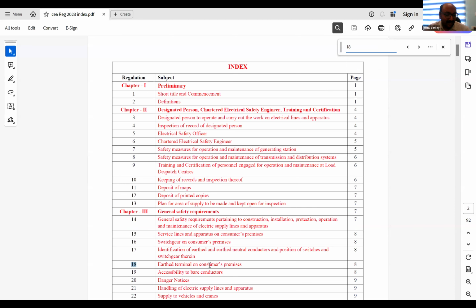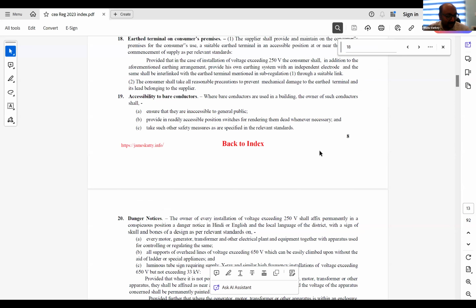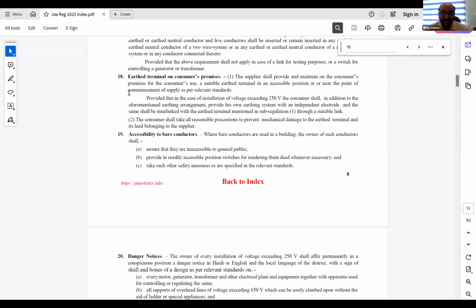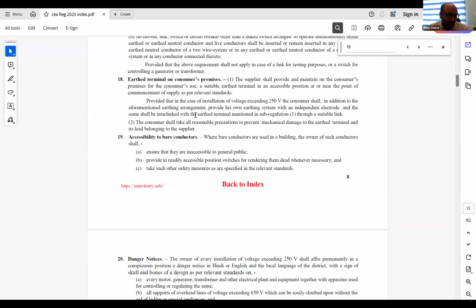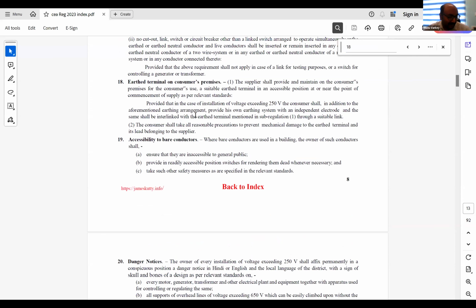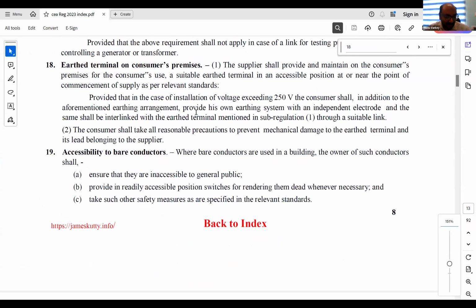Actually, as per Regulation 18, the supplier has to make available an earth terminal within the consumer premises, and the consumer can connect his earth electrodes to this earth terminal. The idea behind it is to provide a reliable earthing connection for the consumer to utilize. If you just see Regulation 18, it seems very easy to implement and would benefit the consumer. But the issue why this is not getting implemented is that once you connect the consumer's installation to the supplier's terminal, whatever faults occur within the supplier's terminal will affect the consumer's terminal, and it can create a dangerous scenario, because most suppliers in our country are not following the regulations with regard to their own equipment.